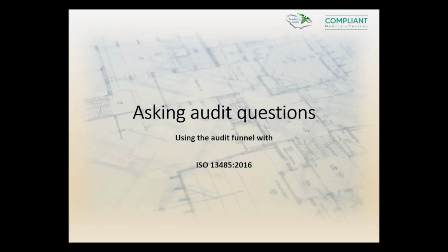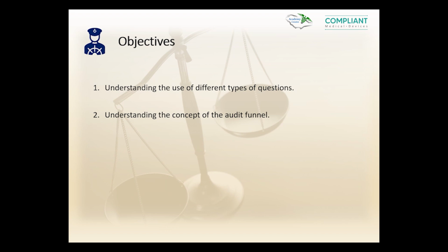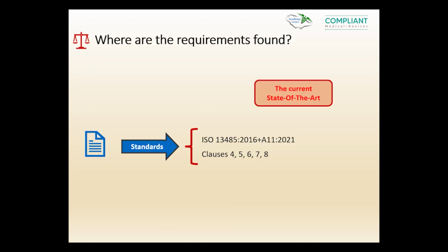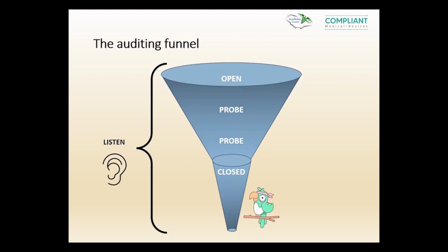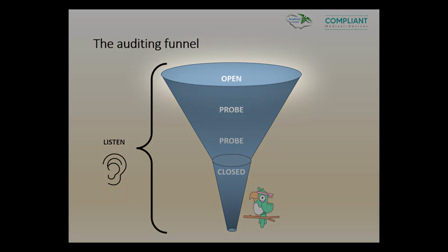The topic for today is asking audit questions using the audit funnel for compliance with ISO 13485:2016. Asking audit questions using the audit funnel with ISO 13485 as your criteria. The objectives are understanding the use of different types of questions and the concept of the audit funnel as a general technique and methodology to follow. Requirements, clause 8.2.4, with respect to ISO 13485:2016. The audit funnel itself, with respect to its methodology, begins with an open question.